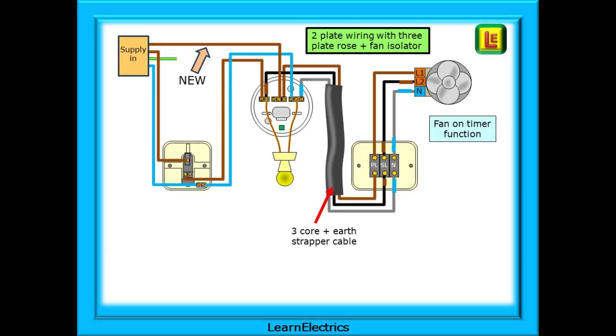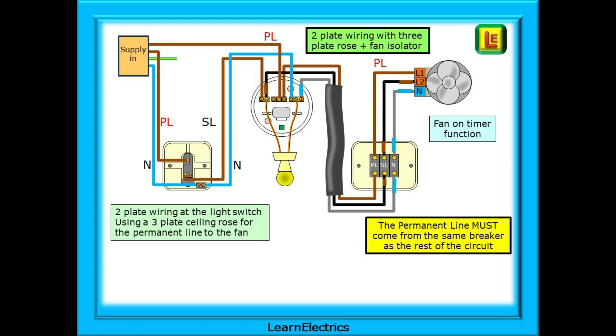In this example we've run a new PL wire from the circuit breaker to the ceiling rose. Now using three core strapper cable we can run a permanent line, switched line and neutral to the isolator switch and then to the fan. An important point here. The new permanent line conductor must come from the same circuit breaker as the rest of the circuit. We must not borrow a permanent line from a convenient supply nearby. That is bad practice and may lead to harm.